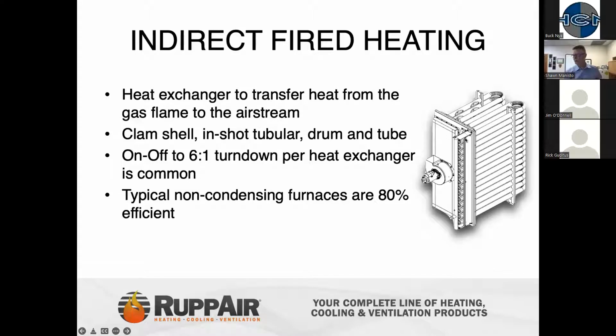Now we've got in-shot tubes, or in the case of large indirect fired air handling systems, you're going to have what's called a drum and tube, basically like a big barrel they'd fire a burner into and then run it back through some secondary bypass tubes. Traditionally, indirect fired systems are going to be anything from an on-off control to a 6-to-1 turn down on a single exchanger. Today, you'll get higher turn down capabilities off of indirect fired units by doing split burner capacities on the in-shot style burners, or maybe going to multiple heat exchangers within a package.